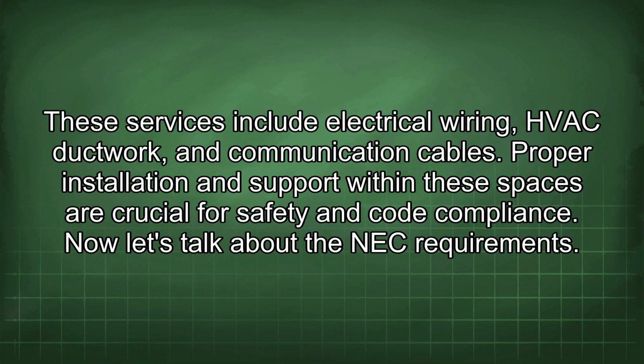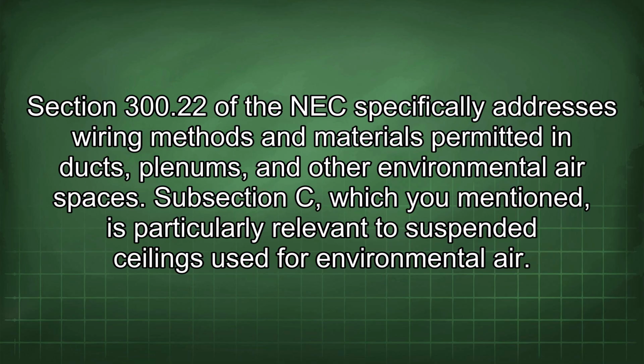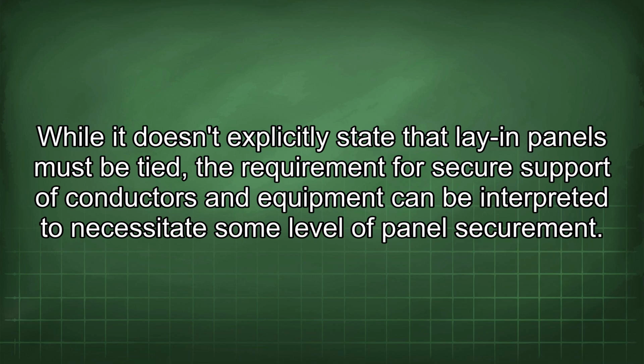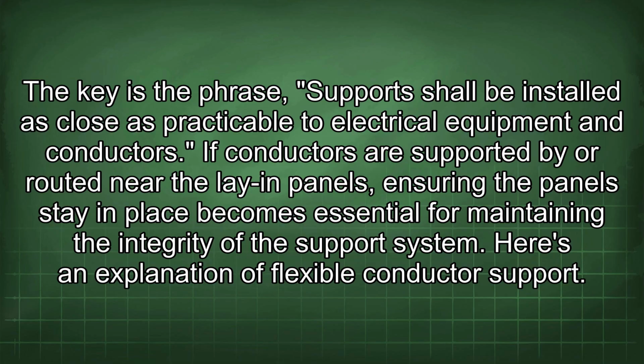Now let's talk about the NEC requirements. Section 300.22 of the NEC specifically addresses wiring methods and materials permitted in ducts, plenums, and other environmental air spaces. Subsection C, which you mentioned, is particularly relevant to suspended ceilings used for environmental air. While it doesn't explicitly state that lay-in panels must be tied, the requirement for secure support of conductors and equipment can be interpreted to necessitate some level of panel securement. The key is the phrase, support shall be installed as close as practicable to electrical equipment and conductors. If conductors are supported by or routed near the lay-in panels, ensuring the panels stay in place becomes essential for maintaining the integrity of the support system.